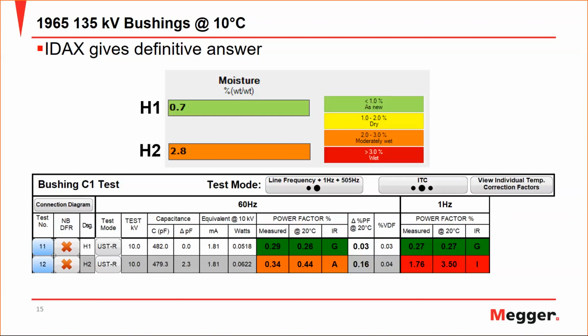Well, we were talking about bushings today, but dry type transformers do not have liquid inside, so the line frequency power factor values are going to be a little bit higher. I don't have that specific answer today, but it is helpful to look at sister assets, sister dry type transformers. If you're only looking at line frequency, then everything that I've presented today holds true, but it's not going to be enough information to make an accurate assessment of that particular transformer.